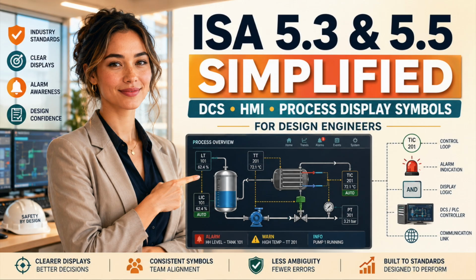Where a command is issued and the expected state is not confirmed, the operator must see the transition, mismatch, or failure condition. A valve may be open, closed, opening, closing, intermediate, failed to open, failed to close, locally controlled, manually positioned, unavailable, or unknown. A motor may be running, stopped and available, stopped and unavailable, starting, stopping, tripped, interlocked, or under maintenance. You do not need to show every state permanently on the primary display, but you must engineer how each relevant state will be represented. Otherwise, the graphic configurator will make those decisions during implementation, and the plant will inherit them for decades.